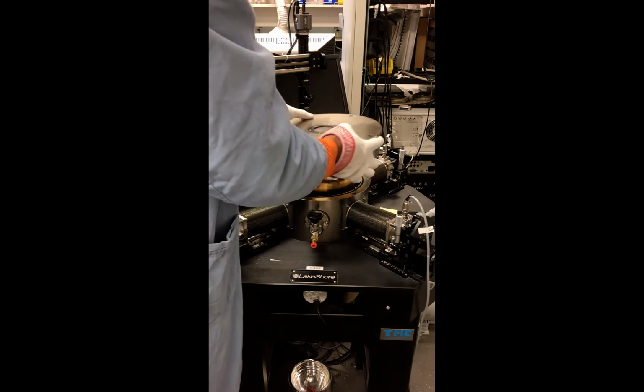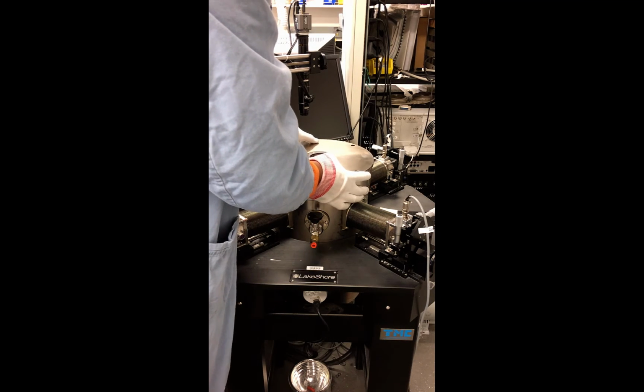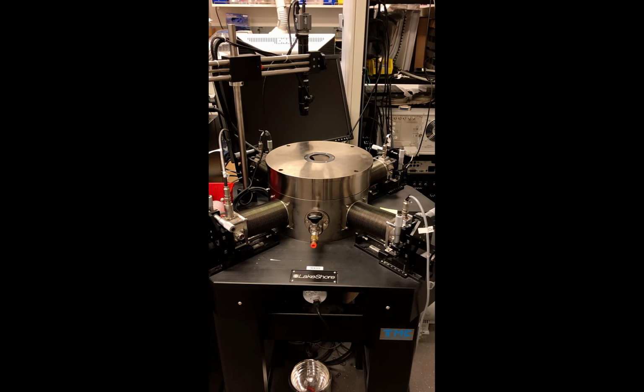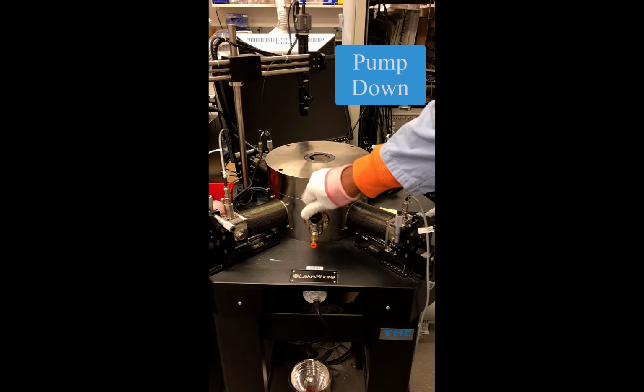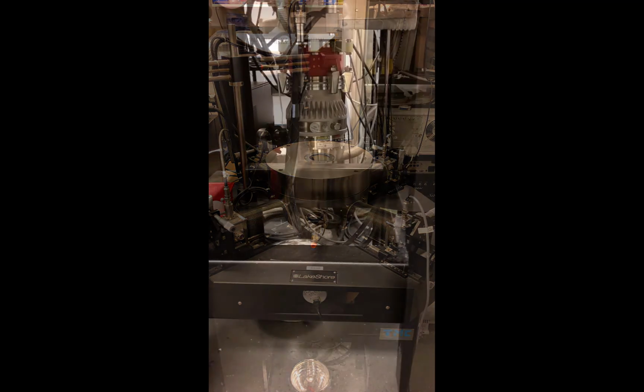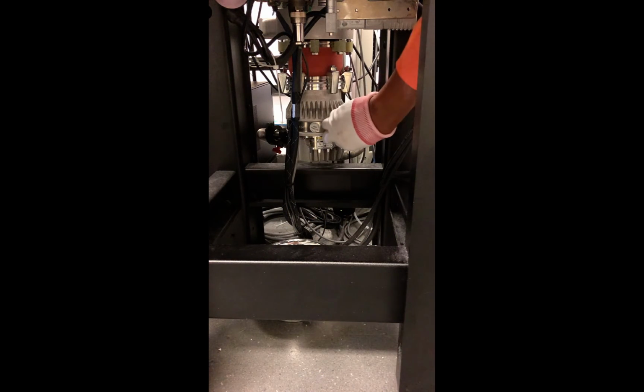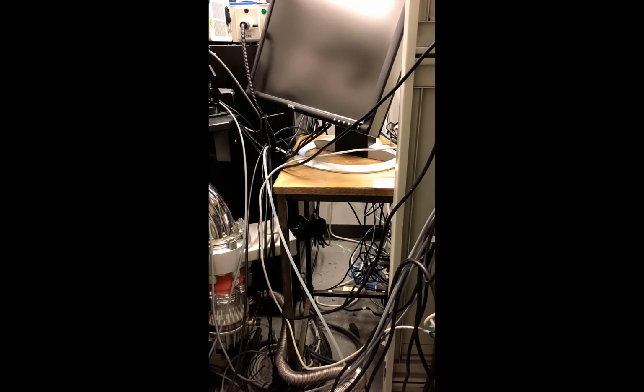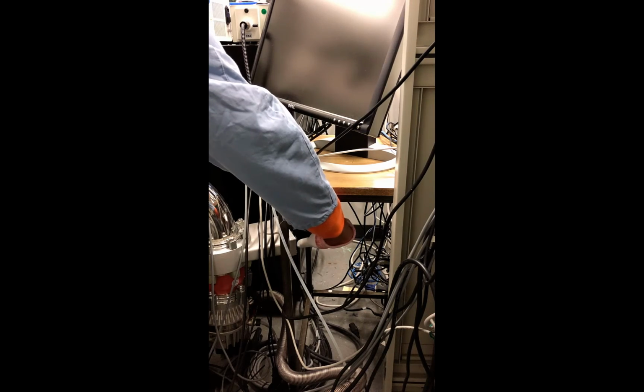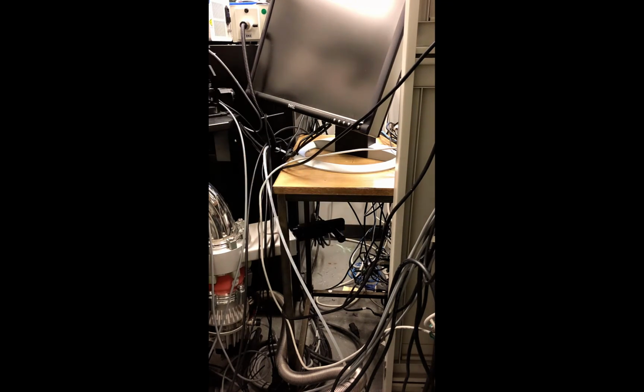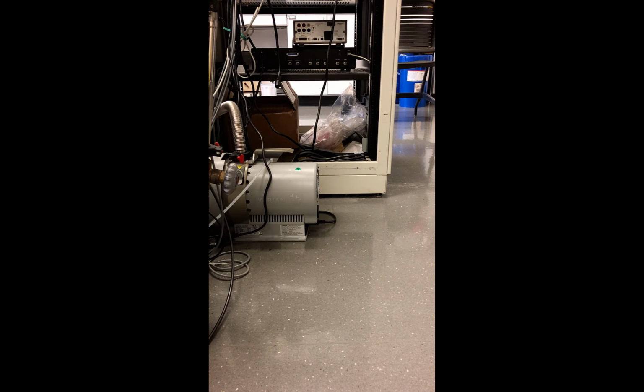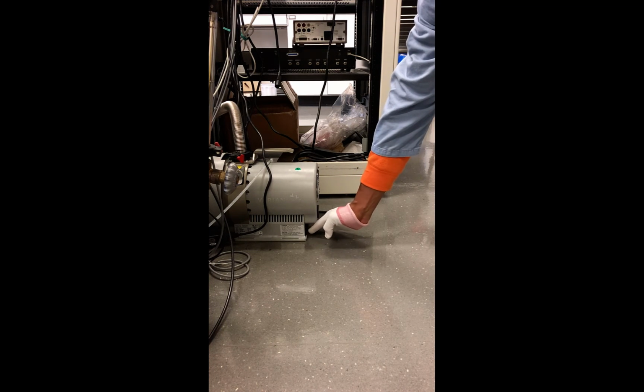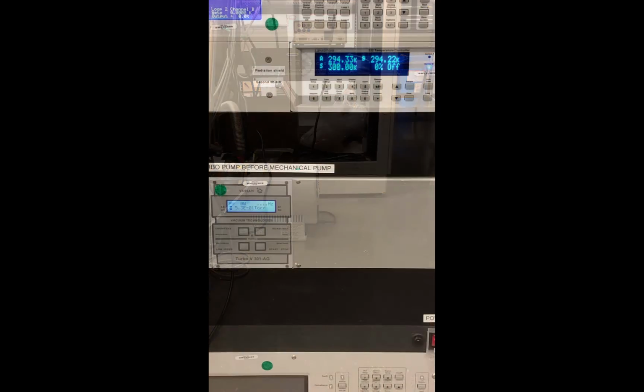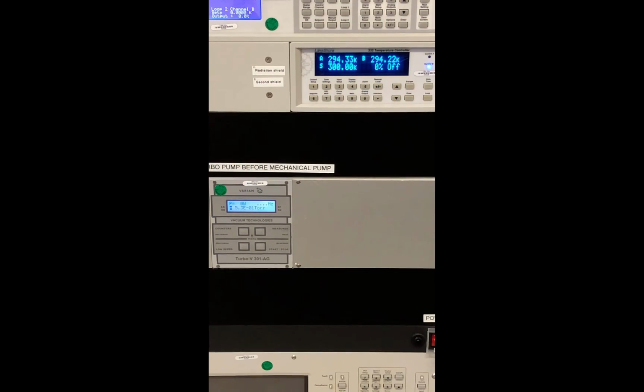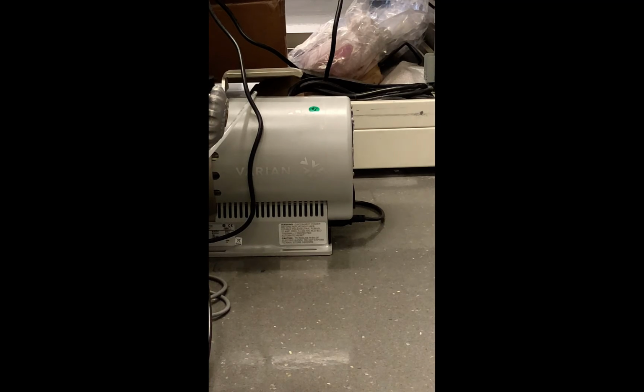Let's put the lid back to prepare for another pump down procedure. Here's another look at that. First, close the sample chamber purge valve. Then close the turbo pump vent valve. Open up the vacuum isolation valve. Then we can turn on the roughing pump. Once the pressure has reached 10 to the minus 1 torr, we can turn off the pump again.